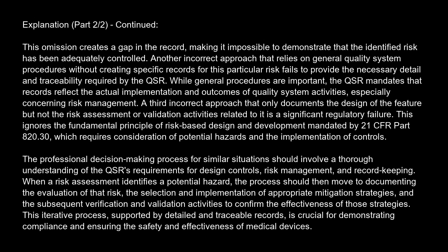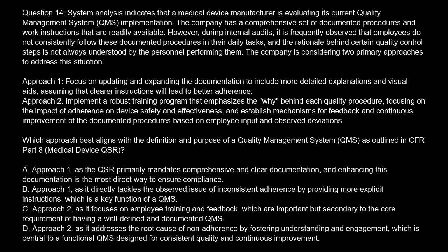The professional decision-making process for similar situations should involve a thorough understanding of the QSR's requirements for design controls, risk management, and record keeping. When a risk assessment identifies a potential hazard, the process should then move to documenting the evaluation of that risk, the selection and implementation of appropriate mitigation strategies, and the subsequent verification and validation activities to confirm the effectiveness of those strategies. This iterative process, supported by detailed and traceable records, is crucial for demonstrating compliance and ensuring the safety and effectiveness of medical devices.